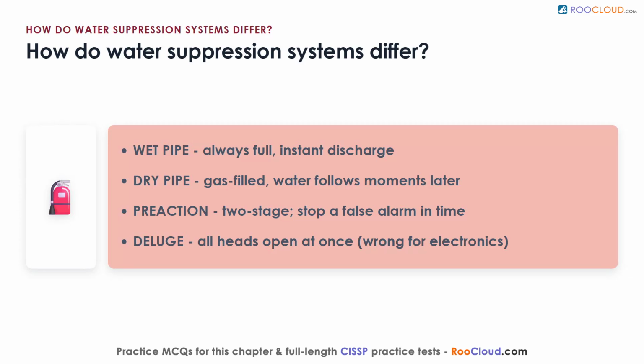A pre-action system adds a two-stage safeguard, filling the pipes only after early fire signs appear and releasing water only after the sprinkler head itself triggers, which lets you halt a false alarm before a drop falls. A deluge system dumps a huge volume through wide-open heads all at once, which is entirely wrong for rooms full of electronics. For a space with both people and computers, the pre-action system is the safe choice, because it gives you a chance to stop a mistake.